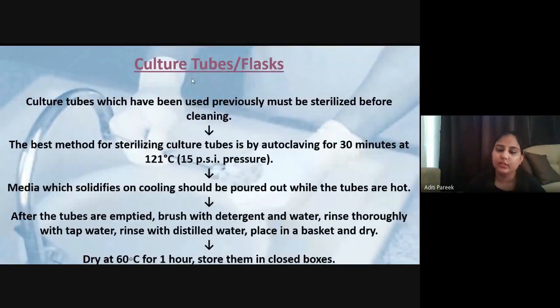For the culture tubes and flask, we generally use culture tubes and flasks or Petri dishes for the culturing purpose, as the name suggests. So they must be sterilized before cleaning. And for this sterilization process, the best method to sterilize culture tubes is by autoclaving them for 30 minutes at 121 degrees centigrade and 15 psi pressure. And we all know this is the standard protocol.